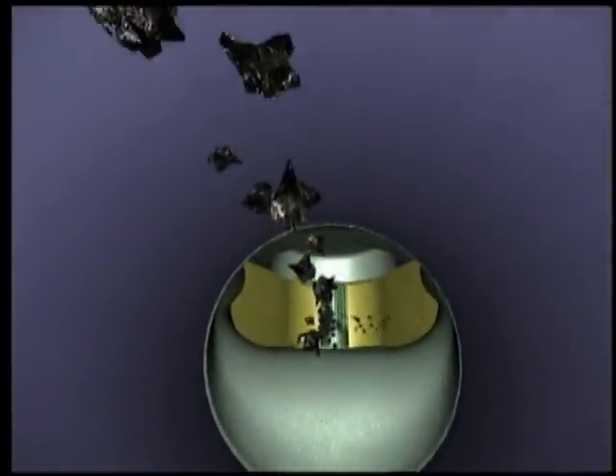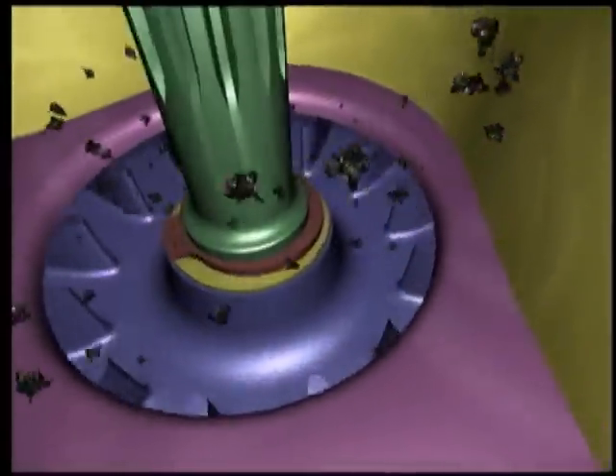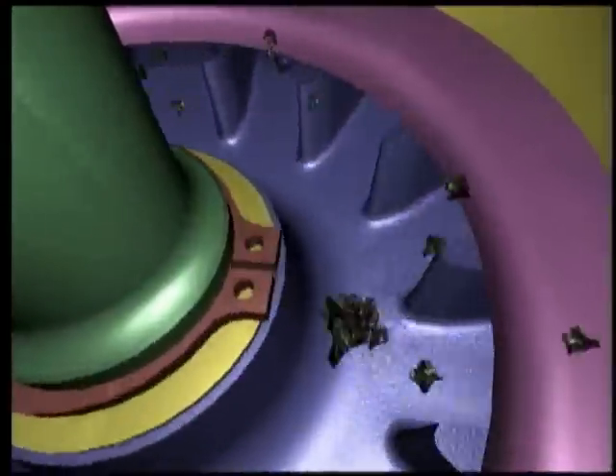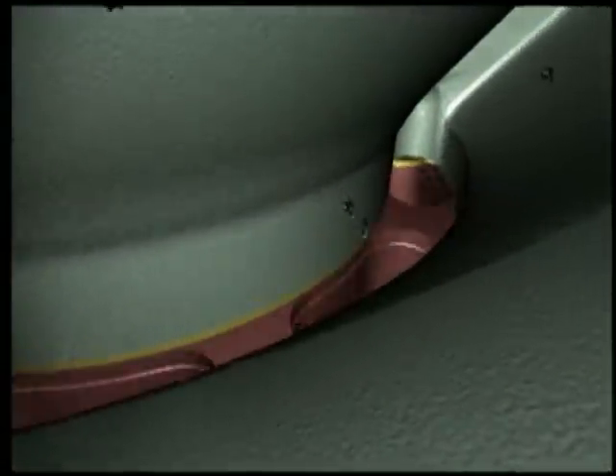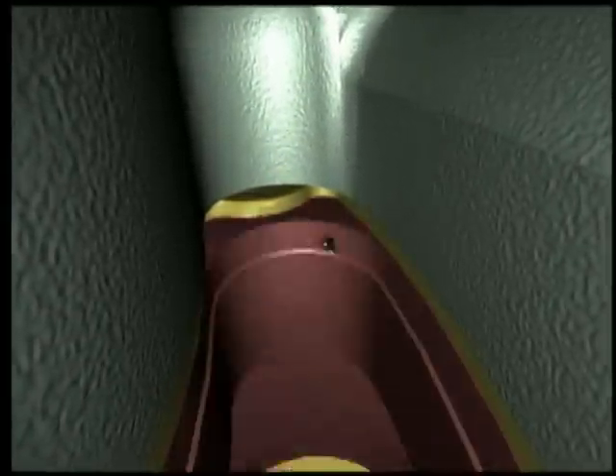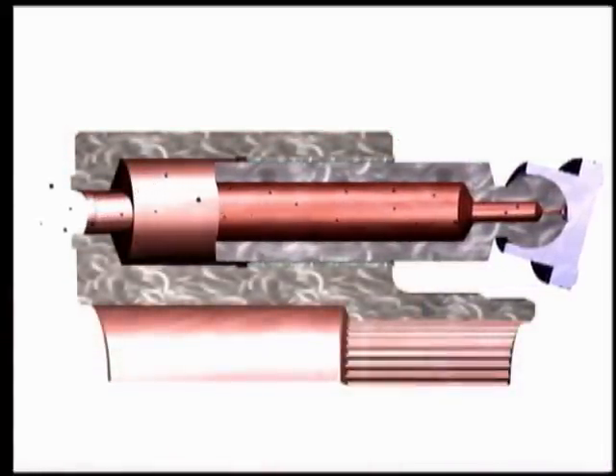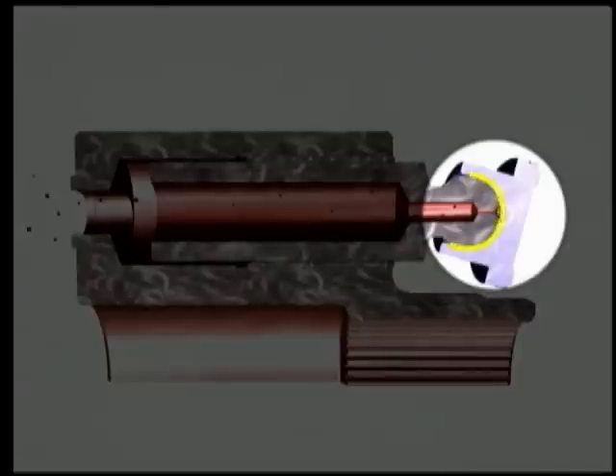Let's follow contaminants in the hydraulic oil as it is drawn from the tank through the hose to the pump. You can see the contaminant's irregular shape with sharp edges and corners. Once the oil and contaminants are drawn into the rotating group of the pump, the contaminants can cause damage in several ways. The larger particles cannot pass through, but will break up as they strike the stationary port plate, shown here in yellow, and accelerate wear. Notice how the contaminants break down the edges of the port plate. Particles can also lodge between the piston and the brass slipper foot, seen in purple, causing it to jam, or the contaminants can scrape walls between the barrel and piston.